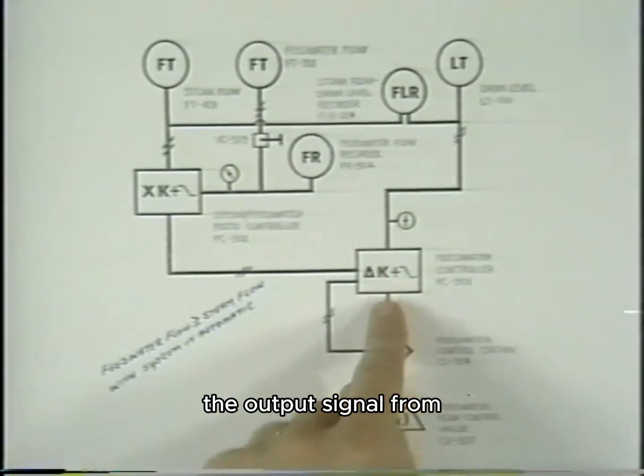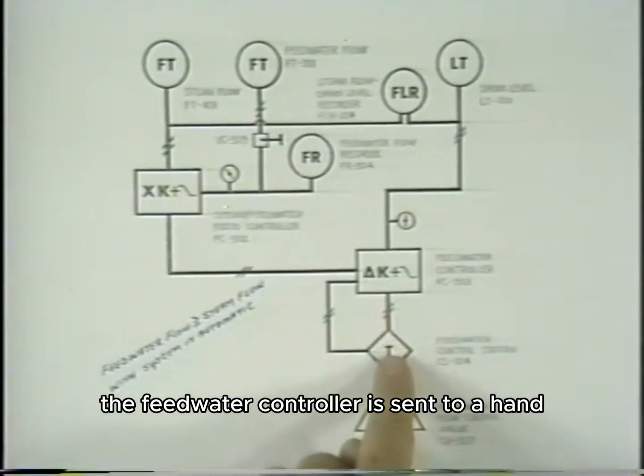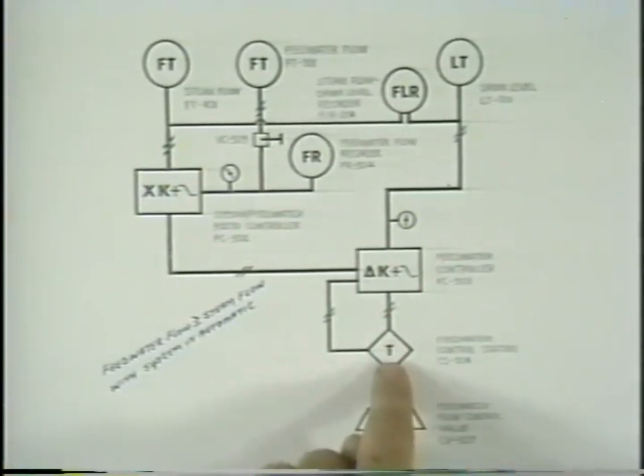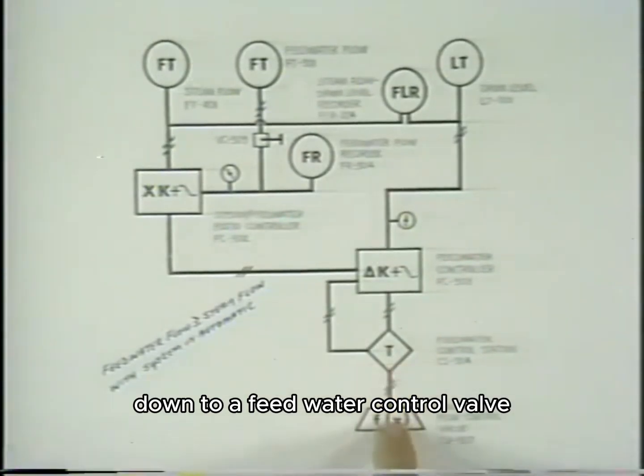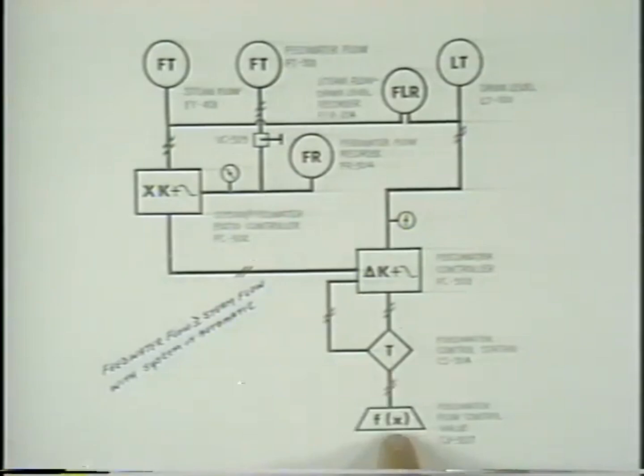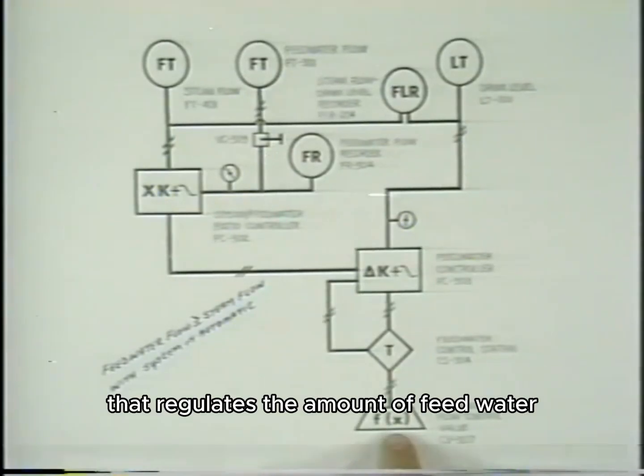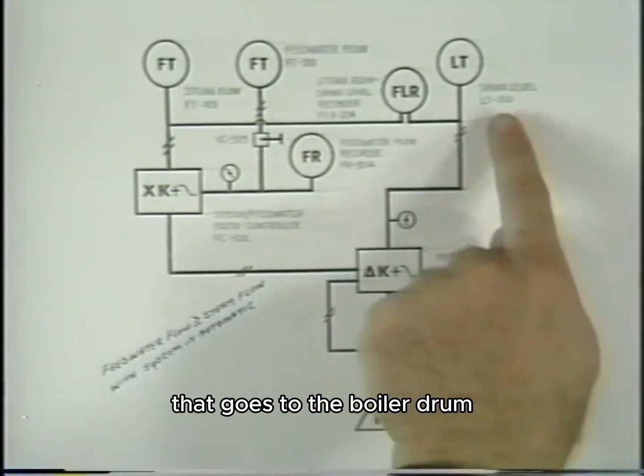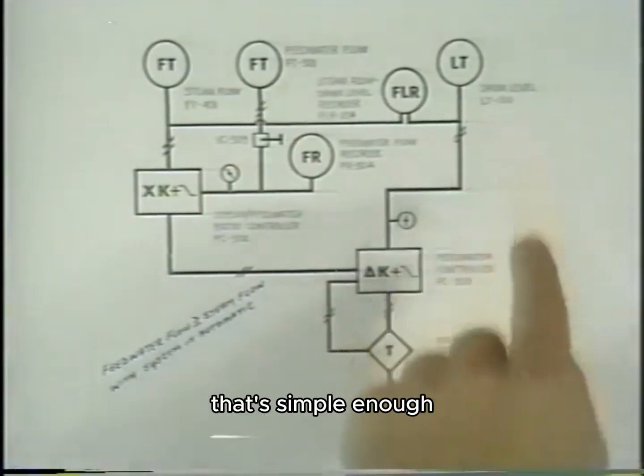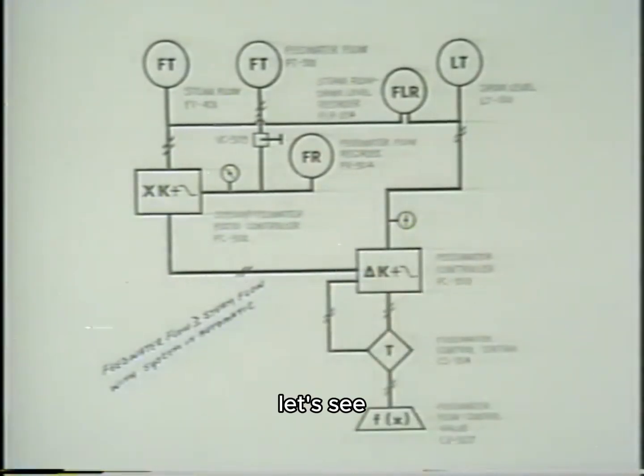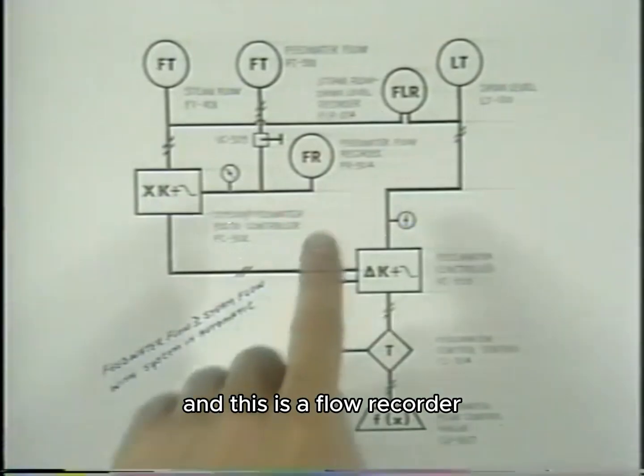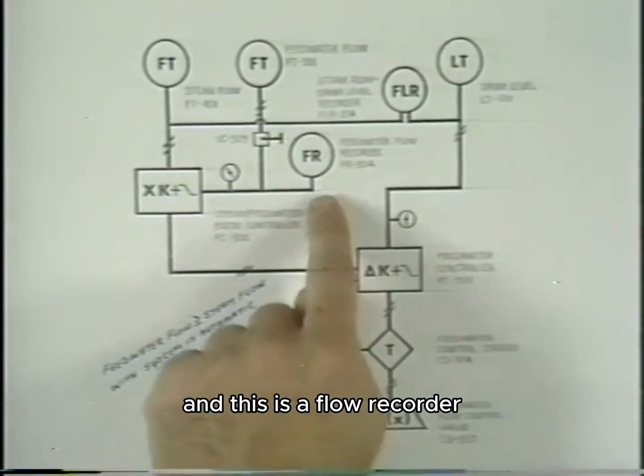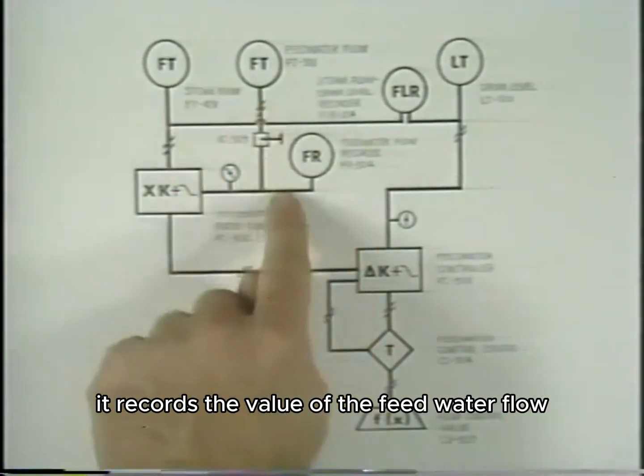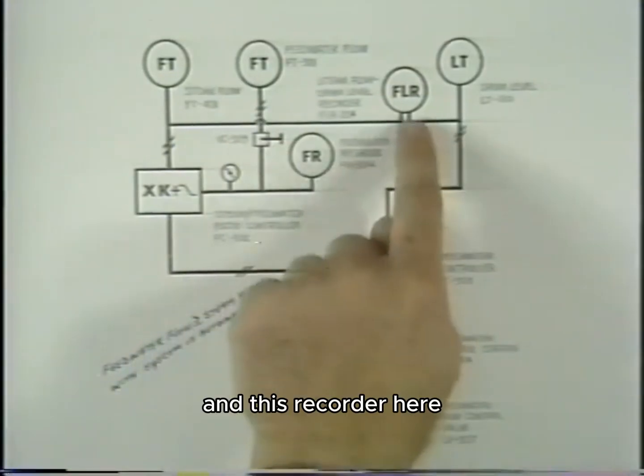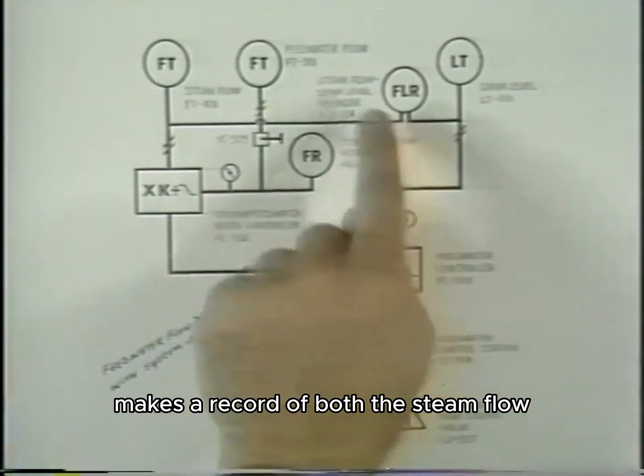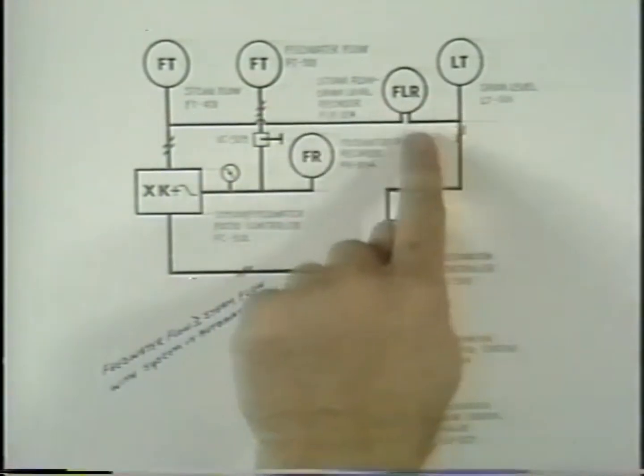The output signal from the feed water controller is sent through a hand auto control station down to a feed water control valve that regulates the amount of feed water that goes to the boiler drum. That's simple enough. Let's see. And this is a flow recorder. It records the value of the feed water flow, and this recorder here makes a record of both the steam flow and the drum level.